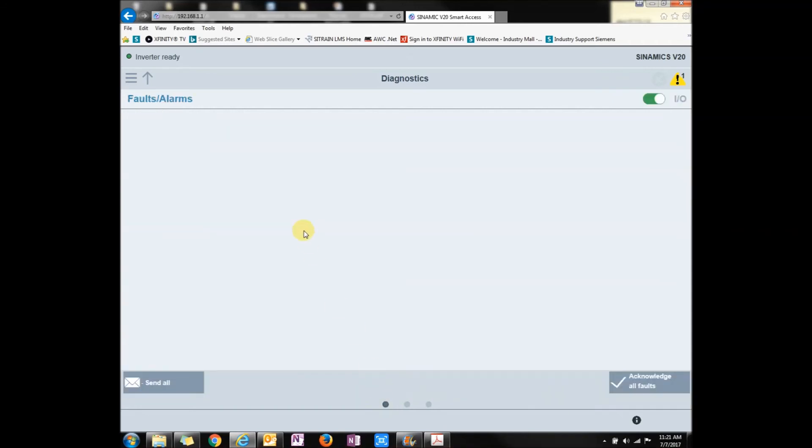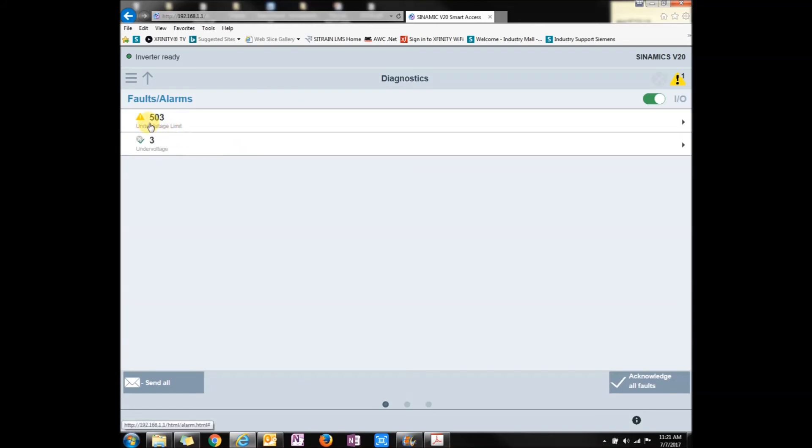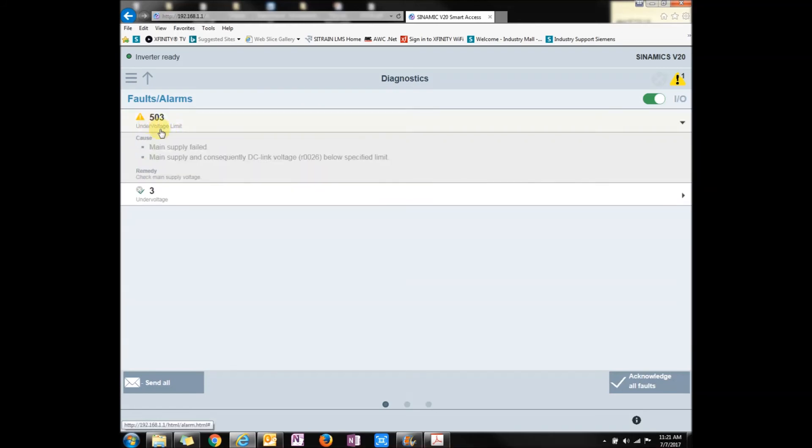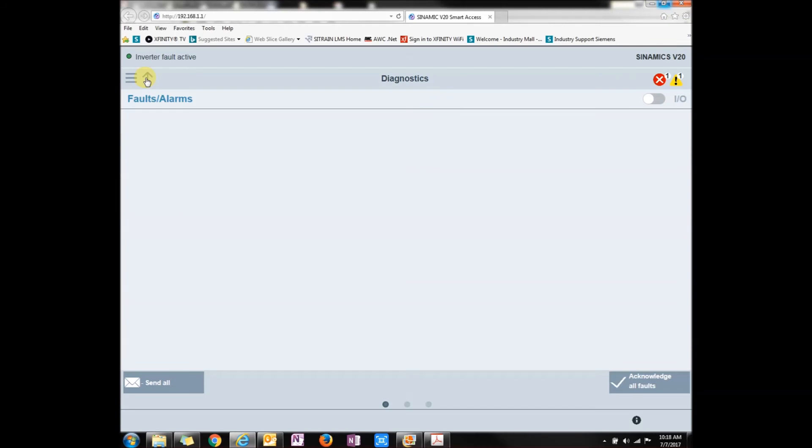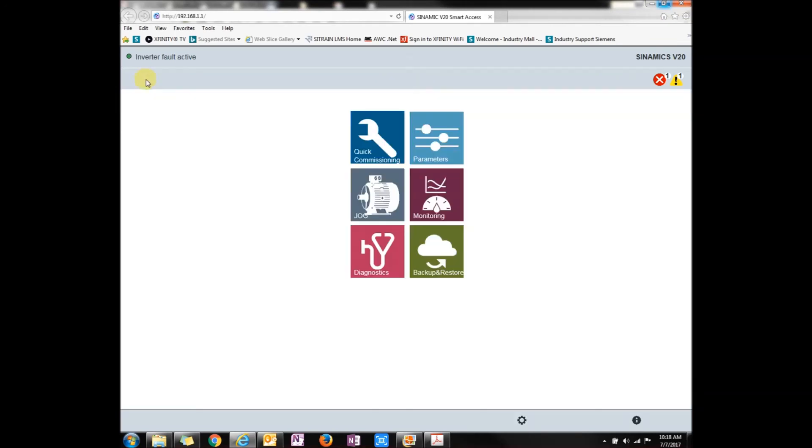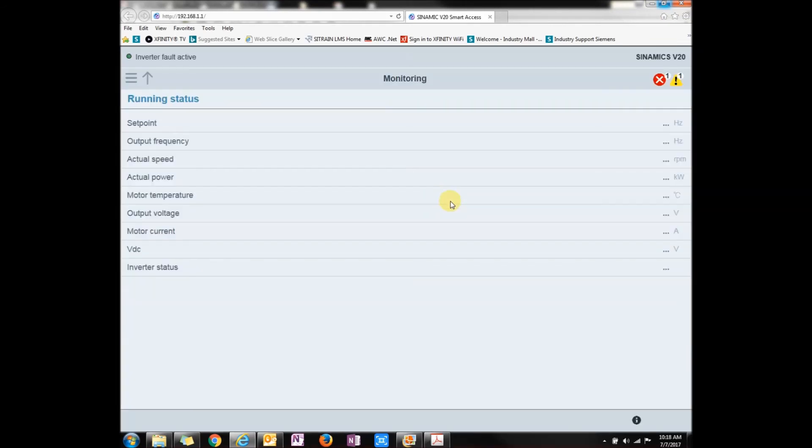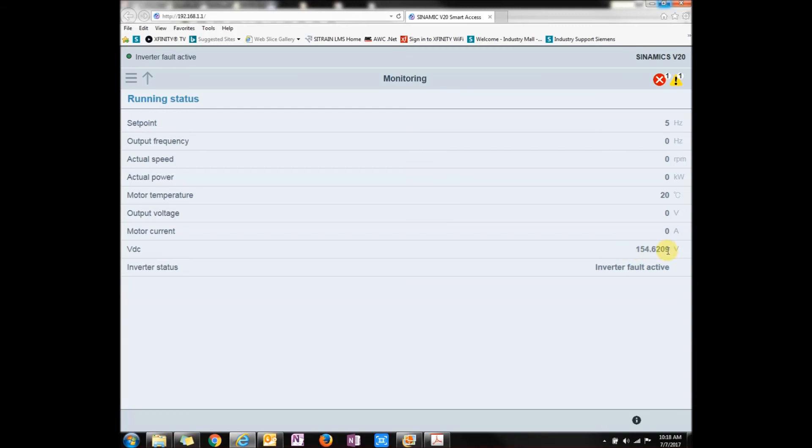The other thing is with the fault screen on the first part, you can click on this under voltage, and it'll say, hey, why don't you see if there's a main supply failure? Well, there is because I'm plugged into a 110. Let me go back up. There's another screen called monitoring. This is where you can look at all the set points and everything that's going on inside the drive, DC voltage. Right now, 150, not good for a drive. It should be 600 at least.